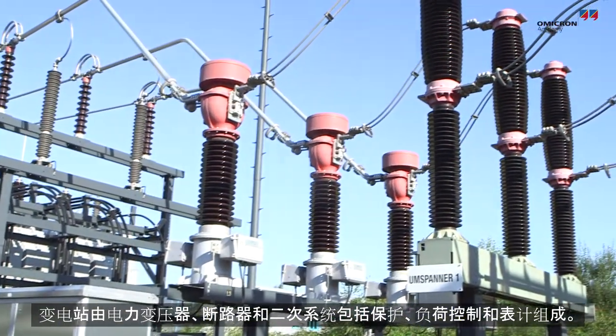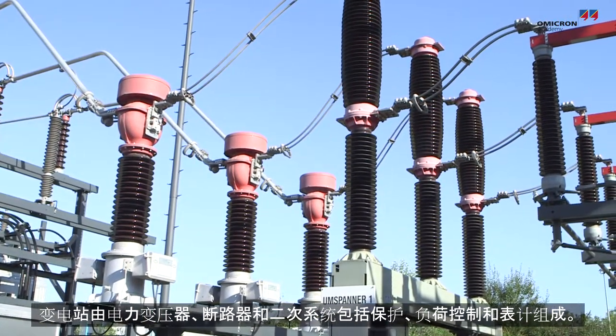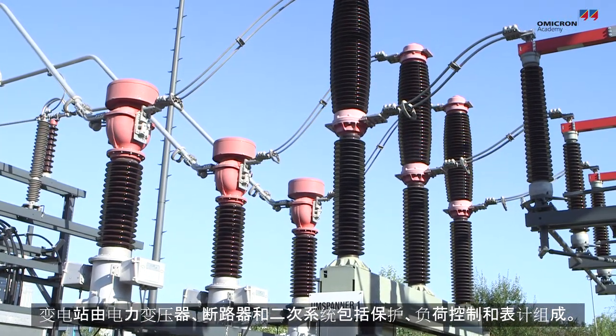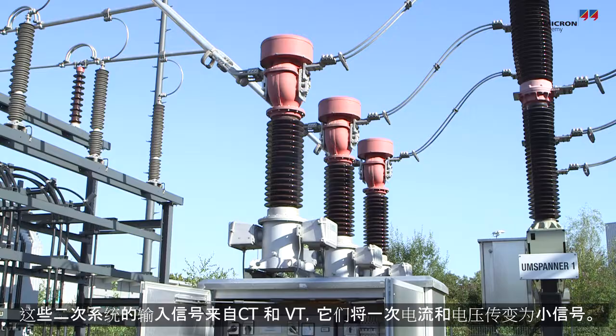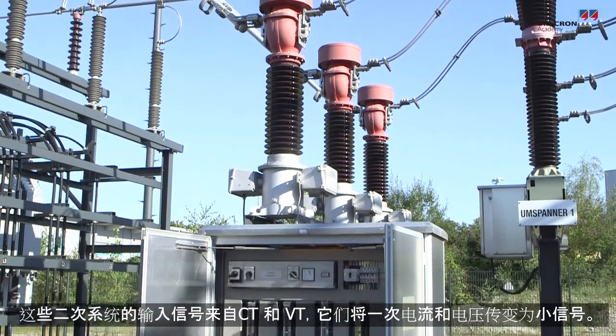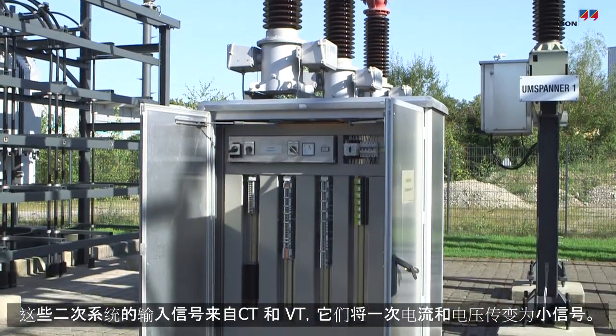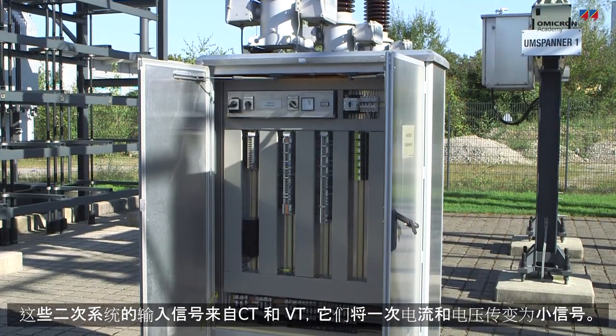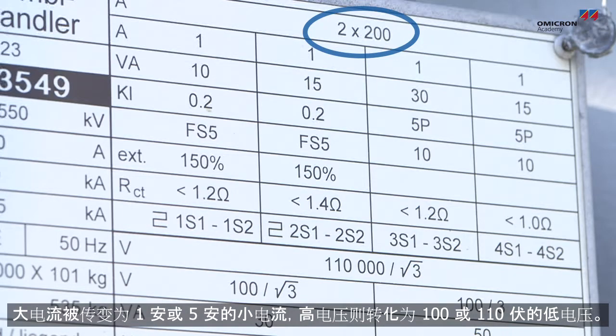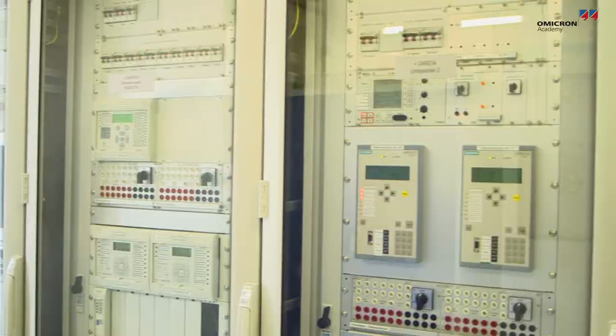In essence, electrical substations consist of power transformers, circuit breakers, and secondary systems for protection, load control, and metering. The input signals for these secondary systems are provided by the CTs and VTs, which transform the primary currents and voltages into smaller signals. High primary currents are transformed into low currents of up to 1 or 5 amps, and high primary voltages into low voltages of up to 100 or 110 volts.